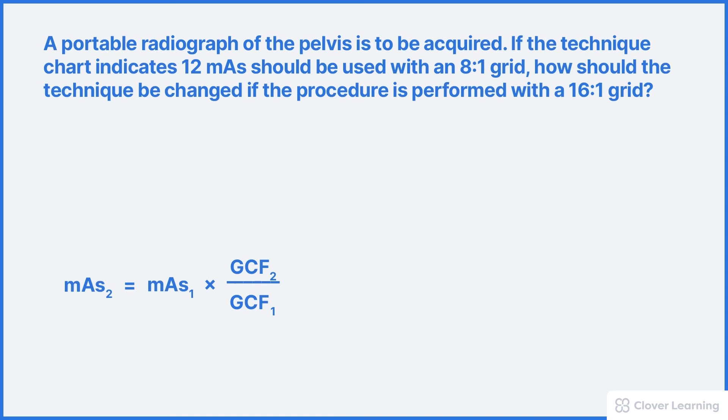Start with the formula and we'll insert all known variables. mAs2 equals mAs1 times grid conversion factor 2 divided by grid conversion factor 1. The prescribed mAs according to the technique chart is 12. The new grid conversion factor for a 16 to 1 grid is 6. The original grid conversion factor for an 8 to 1 grid is 4. So to calculate the new mAs, we just follow the math that's in this formula. The new mAs, that's mAs2, is equal to 12 times 6 divided by 4 which equals 18 mAs.